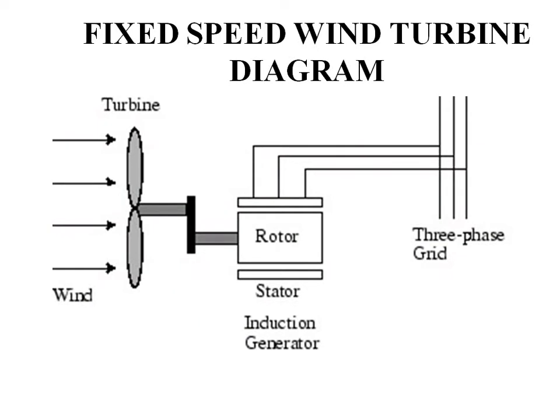And the induction generator based wind energy systems are fixed speed systems. Therefore, it requires reactive power compensation. The main reason for generating reactive power is to provide voltage regulation and improve system stability. Thereby, the losses associated with the system is also reduced. The addition of FACTS device can prevent voltage collapse by reducing voltage sag or swell.